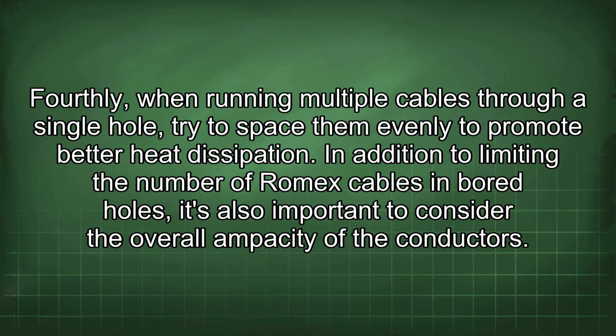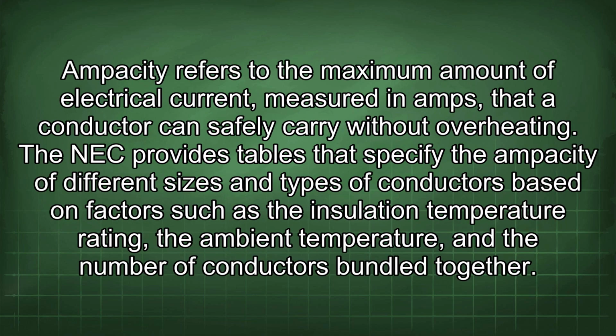In addition to limiting the number of Romex cables in bored holes, it's also important to consider the overall ampacity of the conductors. Ampacity refers to the maximum amount of electrical current, measured in amps, that a conductor can safely carry without overheating. The NEC provides tables that specify the ampacity of different sizes and types of conductors based on factors such as the insulation temperature rating, the ambient temperature, and the number of conductors bundled together.